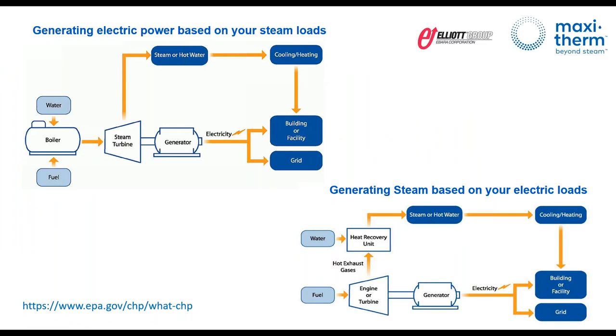And there are two kinds of CHP, of course. The first one, the top left here, is what we will discuss today. And there's the other way, to have a gas generator, for example, take the exhaust gas and use a heat recovery system to generate steam or hot water. The downside of this scenario, the one on the bottom right, is that you need a gas generator for your electric needs. So if you have no steam demand or no hot water demand, you'll be back at 30% efficiency or so.